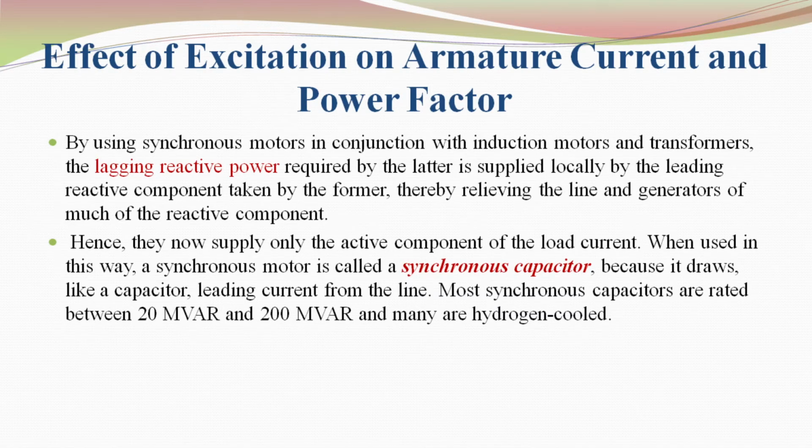So what is a synchronous capacitor? We are using synchronous motors and induction motors in conjunction with transformers. These three things we are using, and the lagging reactive power required by the latter will be supplied by the leading reactive component taken by the former, that is, relieving the line and generators of reactive components. So they will supply only the active component of the load current. These motors are called synchronous capacitors because they draw leading current from the line, like a capacitor.